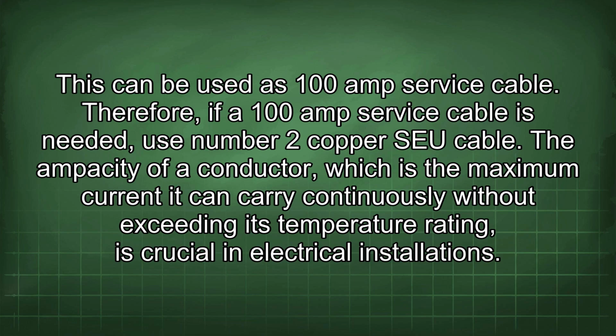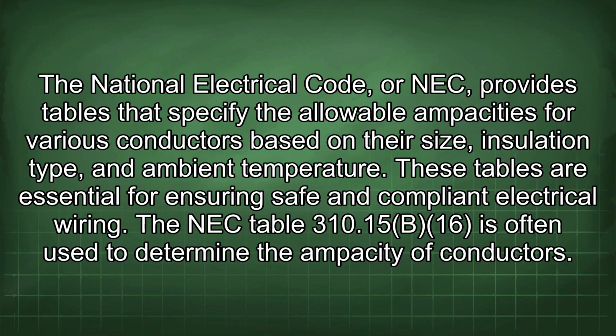The ampacity of a conductor, which is the maximum current it can carry continuously without exceeding its temperature rating, is crucial in electrical installations. The National Electrical Code, or NEC, provides tables that specify the allowable ampacities for various conductors based on their size, insulation type, and ambient temperature. These tables are essential for ensuring safe and compliant electrical wiring.